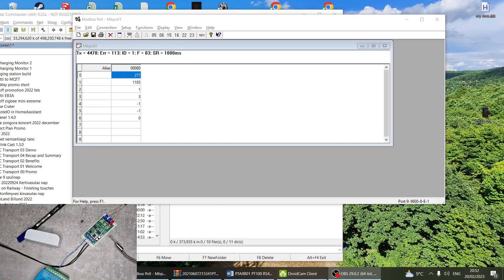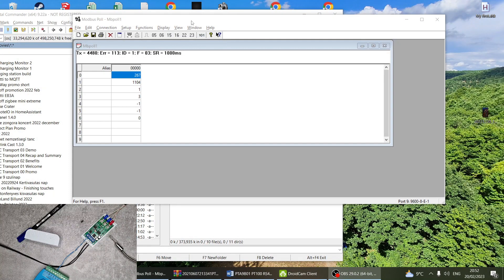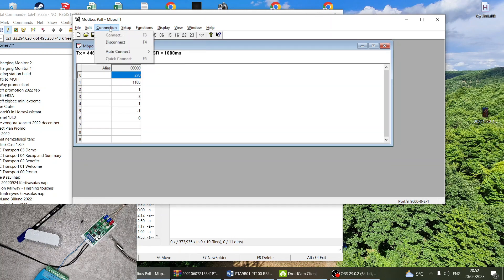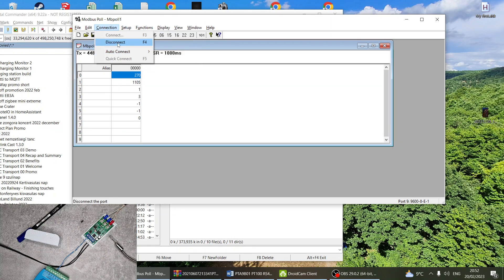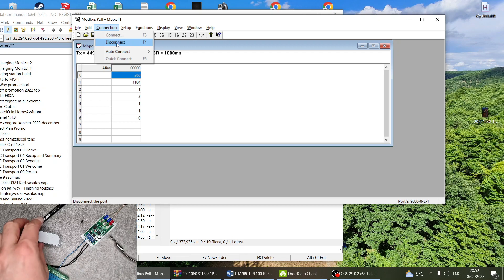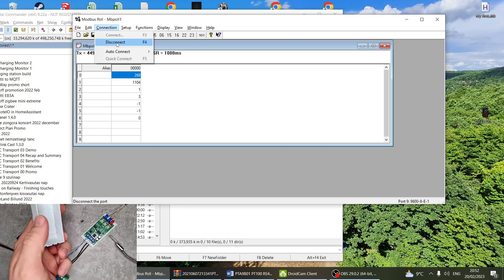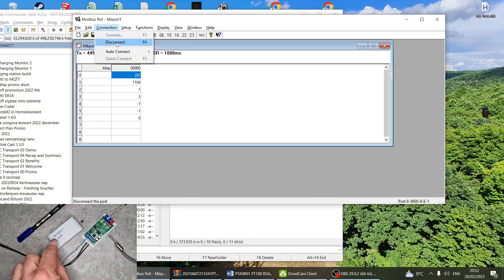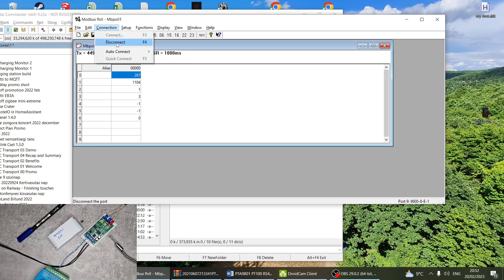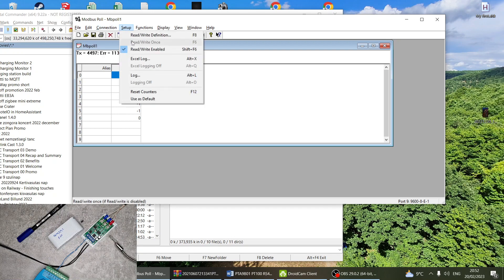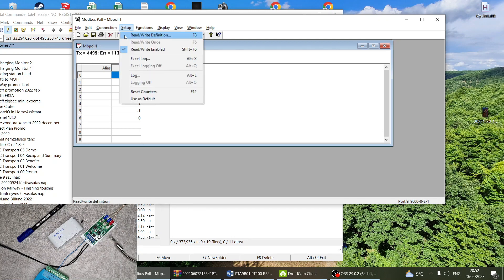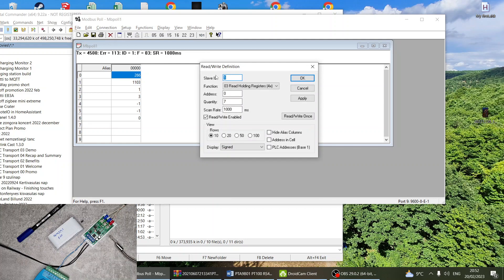What you can see here is I have the Modbus Poll configured and I have the connection set up to use the serial connection. By the way, the note here which says 9600 8N1 is the default connection option, and of course the default address is slave address 1.